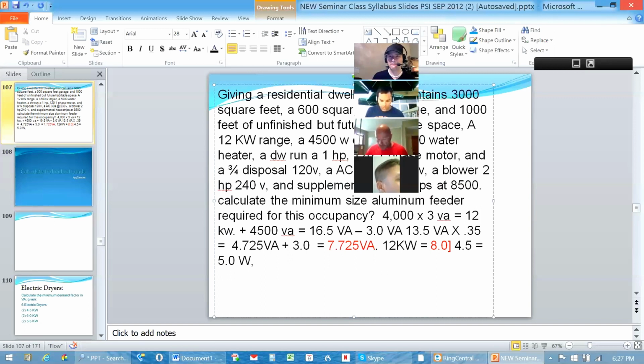Okay. You'll see the same exact kind of mental approach to the space heating as well here in just a second. As a branch circuit, it is considered to be continuous duty, but as a service calculation, which is what we're doing here, it's just 100% of the nameplate rating. So both the water heater and the heating here in a minute, we'll just take at 100%. But right now, we're taking the 5,000 watt water heater, and we're just going to take it as 100% of 5.0 as well. And that is, of course, added to the tally that we've got rolling over there for the other ones. All right. The next thing we're looking at is all those motors, right?